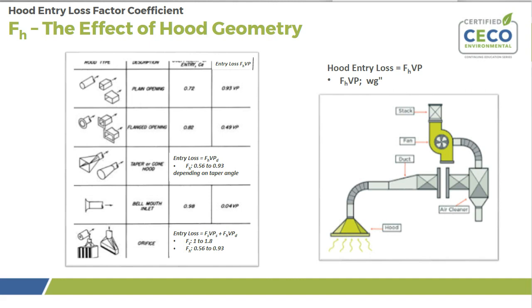The hood entry loss factor varies depending on the geometry of the hood. F sub H accounts for the loss associated with transitioning from the hood area to the duct area. And generally, hoods with tapers and wider entry angles will be more efficient in that they will have less pressure drop at any given flow rate. A bell mouth inlet hood, the second from the bottom there, is the most efficient hood, and it has a hood entry loss coefficient of 0.04.